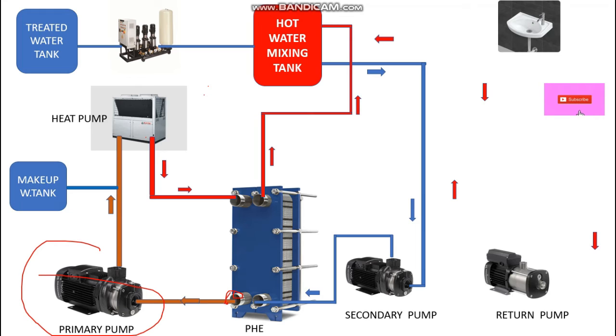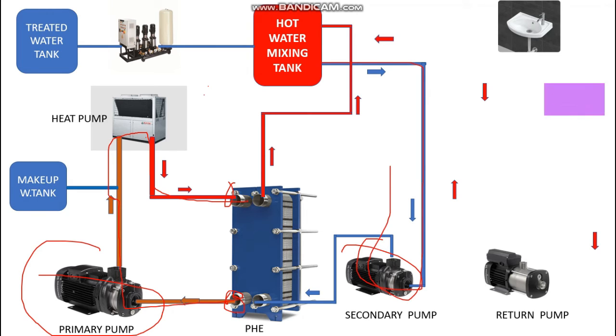Clearly, the work of the primary pump is to take water from the PHE and feed it to the heat pump. The work of the secondary pump is to take cold water from the hot water mixing tank, feed it to the PHE, and at the leaving side it generates hot water which is fed back to the hot water mixing tank.